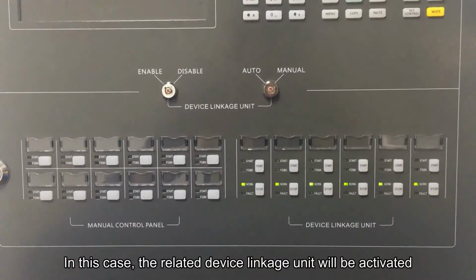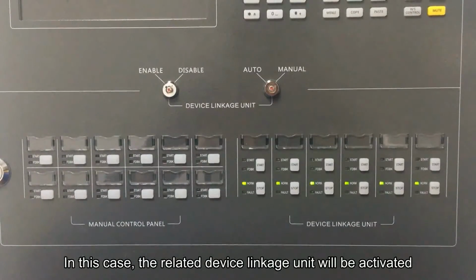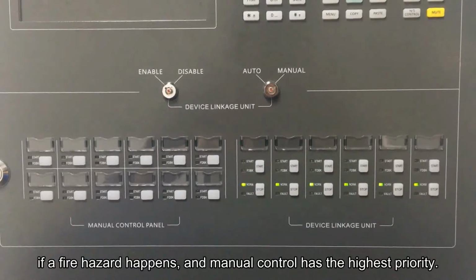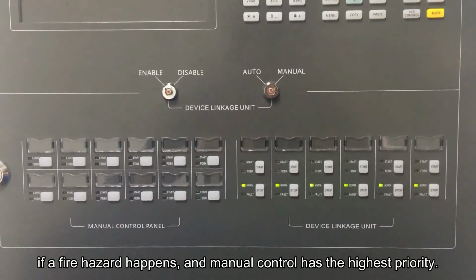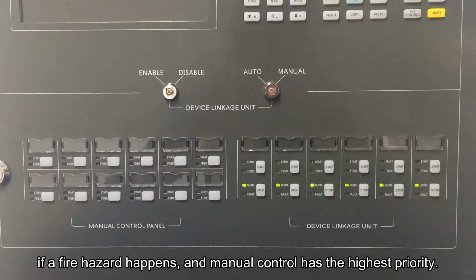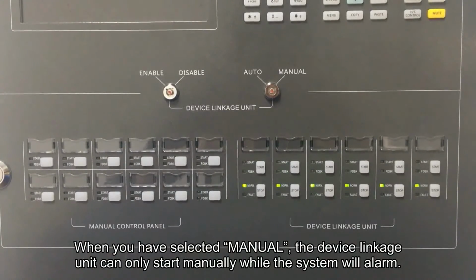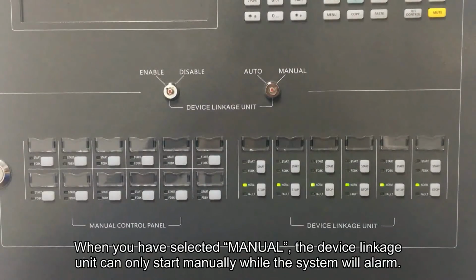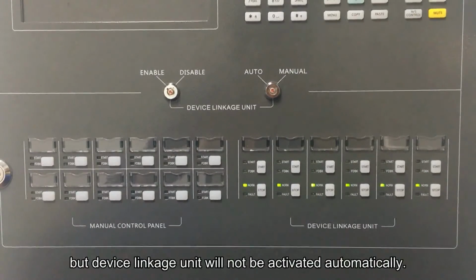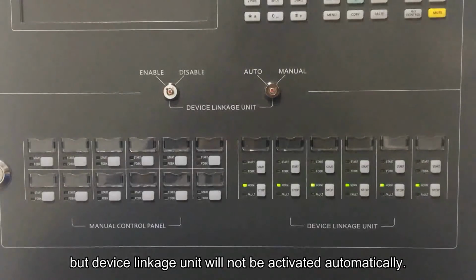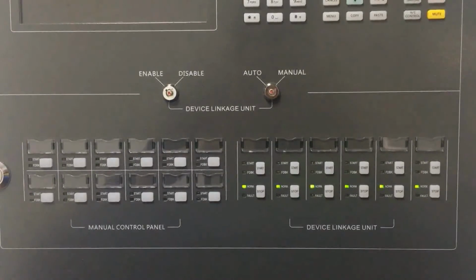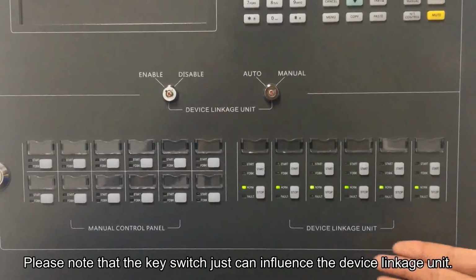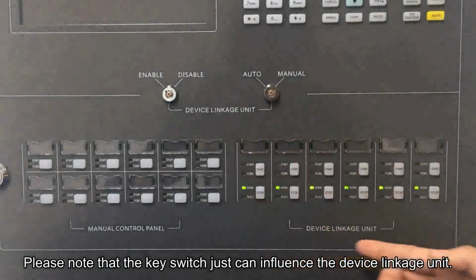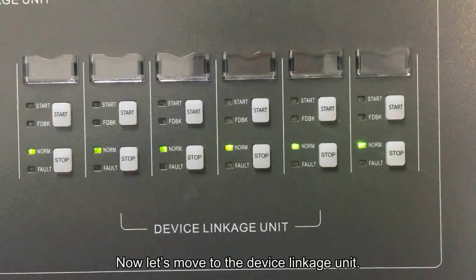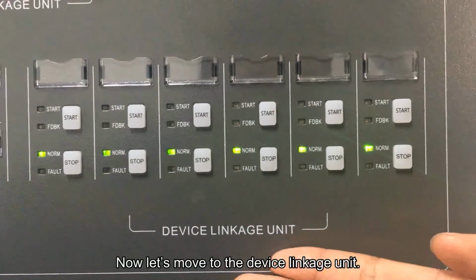In this case, the related device linkage unit will be activated if a fire hazard happens, and manual control has the highest priority. When you have selected manual, the device linkage unit can only start manually while the system will alarm, but device linkage unit will not be activated automatically. Please note that the key switch just can influence the device linkage unit. Now let's move to the device linkage unit.